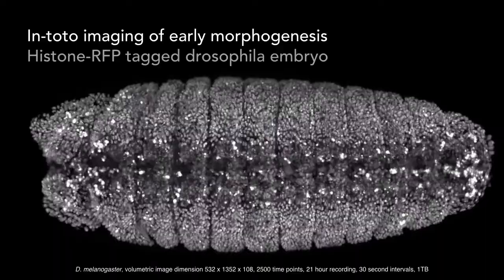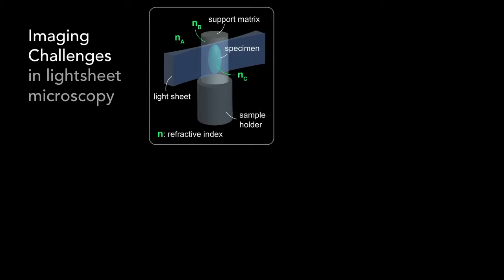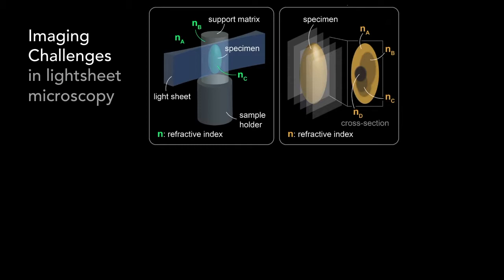And so the question is, how do you achieve this image quality? It turns out that the way we image these samples is inside of an agarose gel. So we put the specimen in agarose matrix, we illuminate that with the light sheet, and we have a variety of refractive indices that bend the light as it enters or leaves the sample. And so this conspires to degrade the image quality dramatically in some cases.